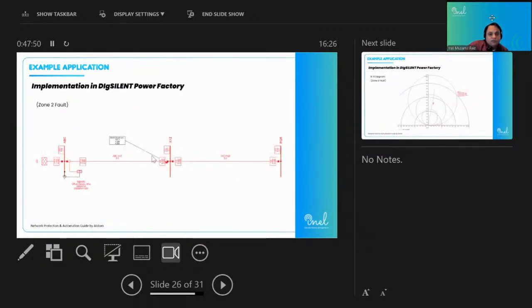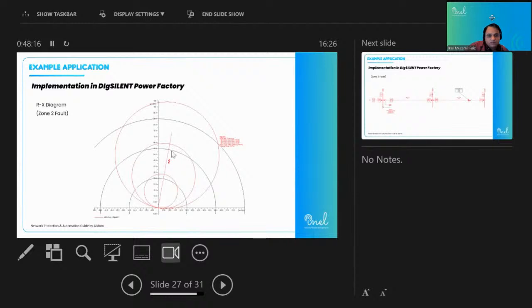For the zone 2 fault, I'm applying the fault at this location, because up to 80% this is zone 1, but after 80% this is zone 2. So I'm applying a fault at this location, which is the XYZ bus bar. This relay will consider it a zone 2 fault, and it will operate after 350 milliseconds or 300 milliseconds, whatever we have set there. You can check that this is a fault in zone 2, and this is the time delay we have set for zone 2.